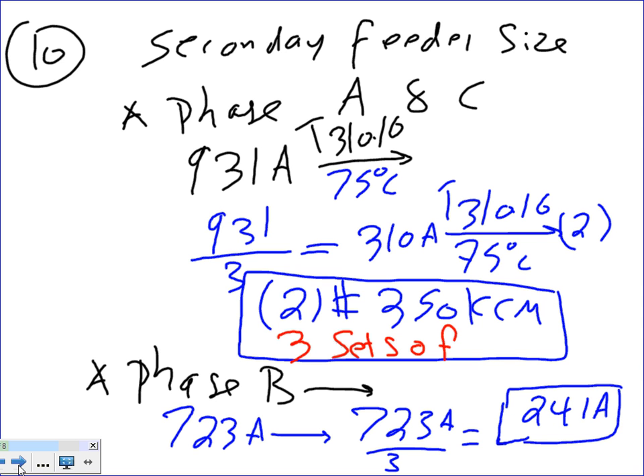350s? You divide by 3, 310 amps. These conductors, 310 amps. Yep. And then 2, 350. 2 conductors, 350 each, 3 sets. Is that 350s? 3 350s in every phase, yes. 3 conductors, 350s in every phase.